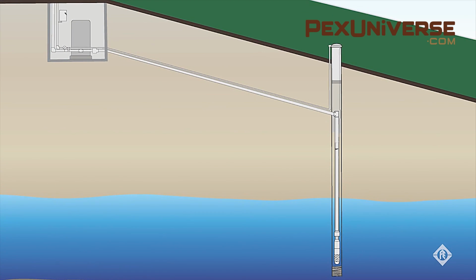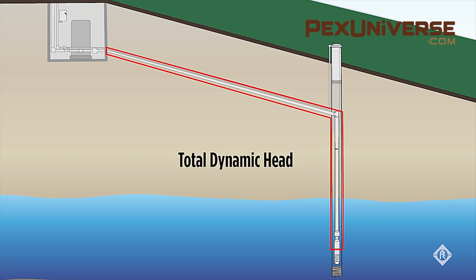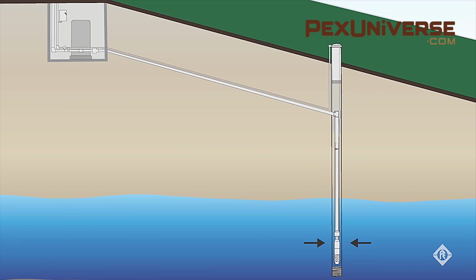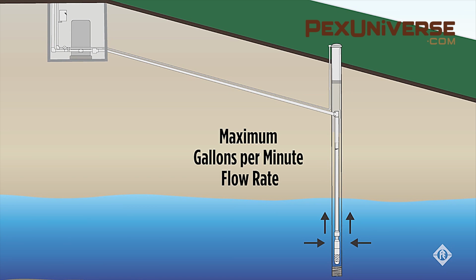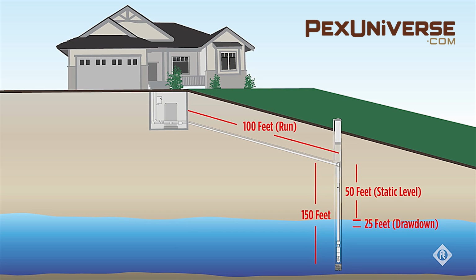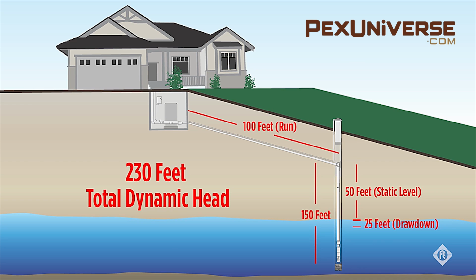The head pressure of a pump describes the maximum height that the pump will move water. For instance, a sump pump with a 15-foot max head, also called a shutoff head, will pump water up to 15 feet before it completely loses flow. Each pump has a characteristic known as pump curve, which indicates how much water in GPM the pump can discharge at a given height, which is feet of head. In this example, we estimate 230 feet of total dynamic head, and we're looking for a 10-gallon pump so that we can look at the chart.